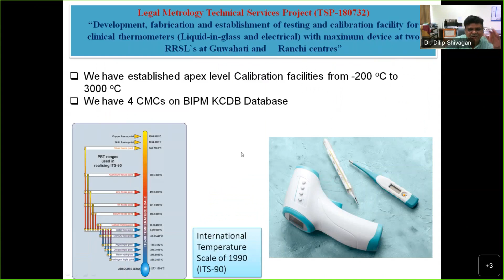These are the measurement uncertainty parameters that we have to critically take into account. Although the acceptance criteria is 0.3 degrees Celsius, say in the case of LiG thermometers, if you have plus minus 0.1 as an acceptance criterion, the source level uncertainty should be below 0.03. So three times, quite large, better than what we are looking for. Similarly, for the IR thermometer black body, it was required to be less than 0.07. With lots of effort during the first phase of COVID, we could establish this up to even 0.05, and critically resolved. Ashutosh sir also has given quite good inputs, and I think we could serve more than 75 models that we could measure at CSIR NPL.